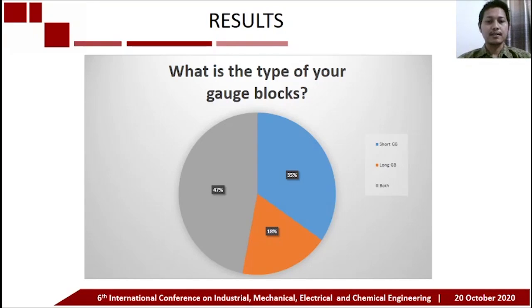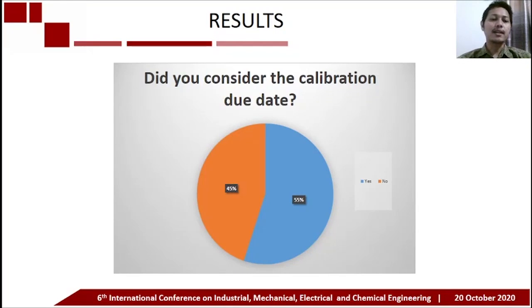From the survey result, 35% of respondents have gauge blocks of the short type, 18% of respondents have gauge blocks of the long type, and 47% of respondents have both types of gauge block. The gauge block standard owned by respondents needs to be calibrated periodically. According to clause 6.4 of the ISO/IEC 17025 standard, the laboratory shall establish a calibration program, which shall be reviewed and adjusted as necessary in order to maintain confidence in the status of calibration.